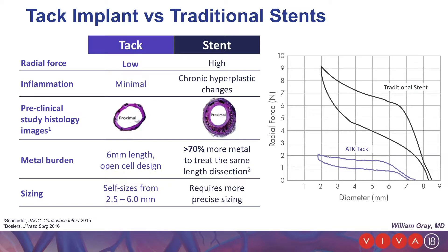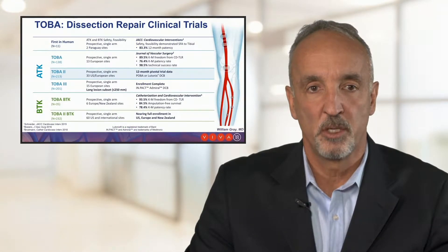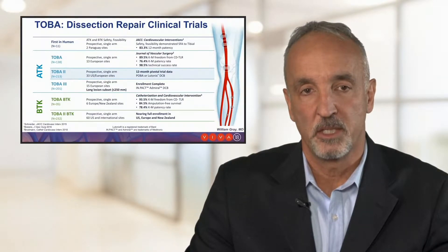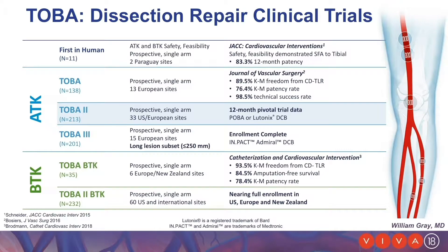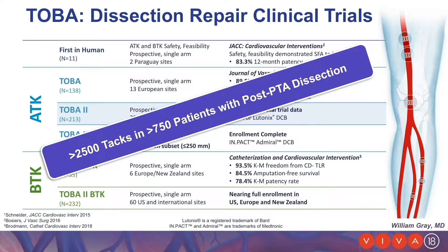Sizing is also much easier. A single device will treat a vessel size from 2.5 to 6 millimeters, as compared to a stent which requires a much more precise sizing matrix. Before we get into the TOBA II trial, it's important to recognize where the TOBA II pivotal trial fits in the larger cadre of trials being done with this device. The TOBA II trial is the pivotal trial for the above-the-knee application, and the TOBA II BTK pivotal trial has nearly completed its enrollment. In total, over 2,500 TACs in 750 patients with post-PTA dissection have been implanted in the clinical regulatory research environment.